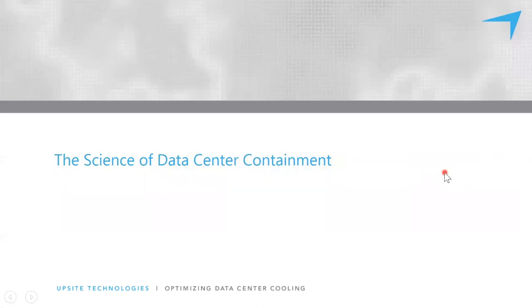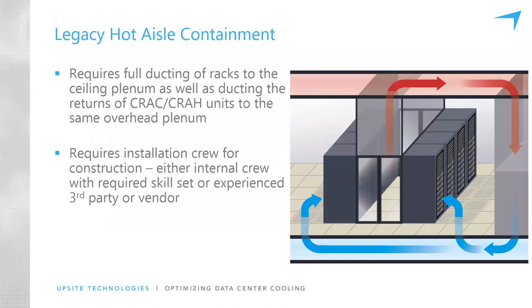Let's move into a little bit of the science of containment and show you some schematics of the airflow paths. With legacy hot aisle containment, we're fully containing the hot air, ducting it to a ceiling plenum, and that is returning to the cooling units that have also been ducted to that ceiling plenum. So we're forcing this flow path through the room.